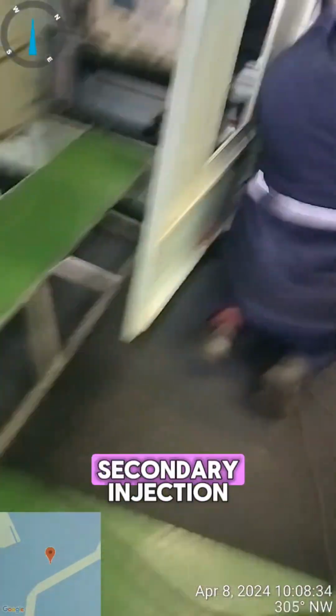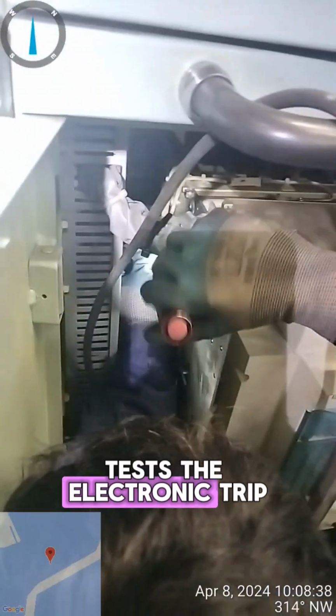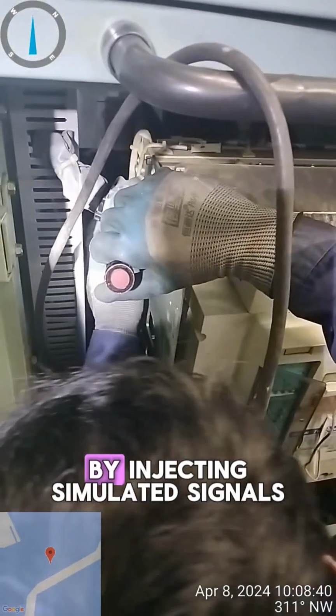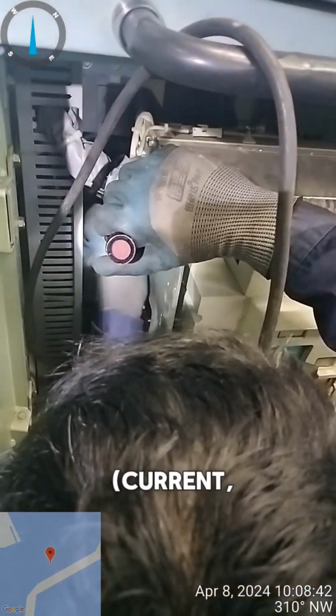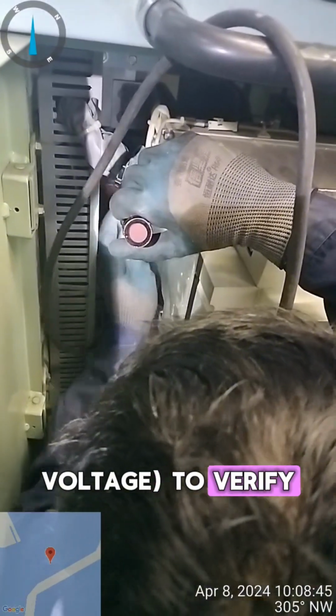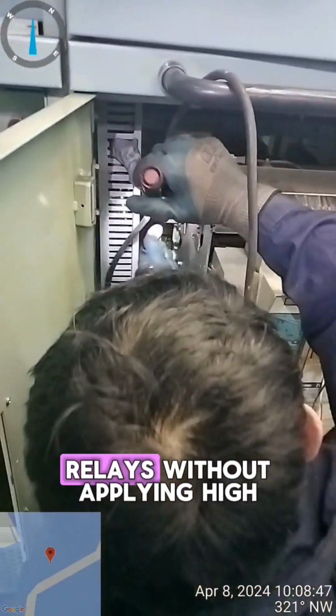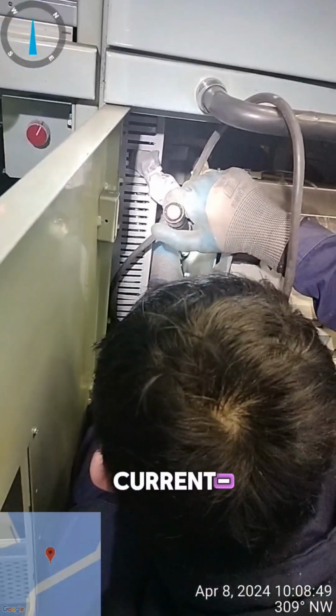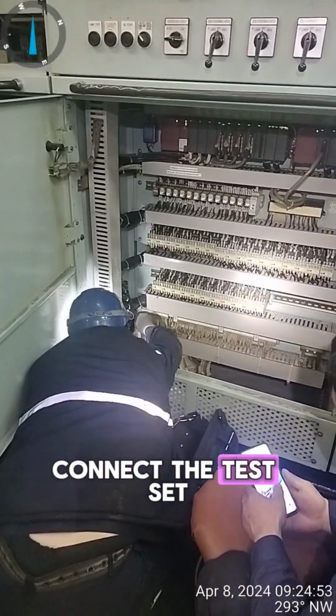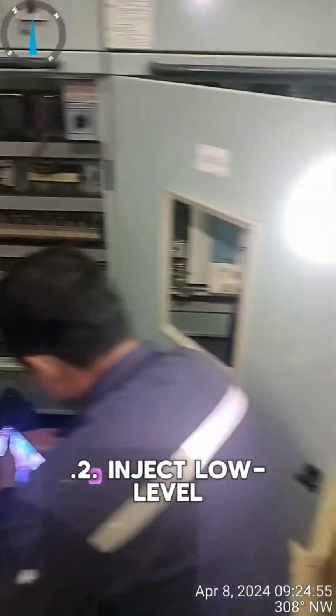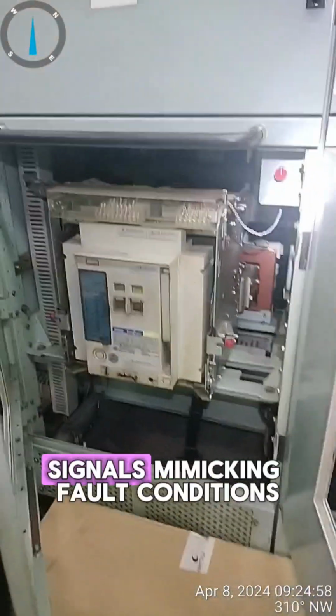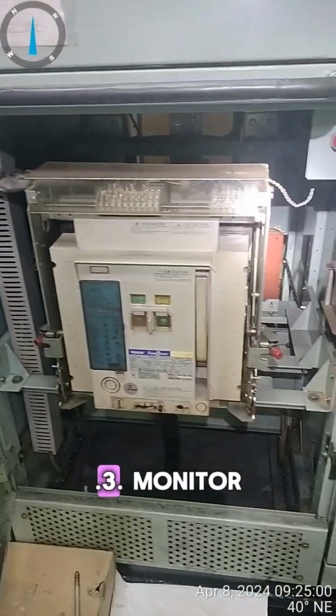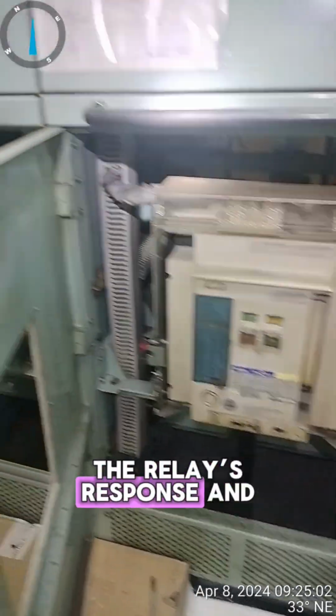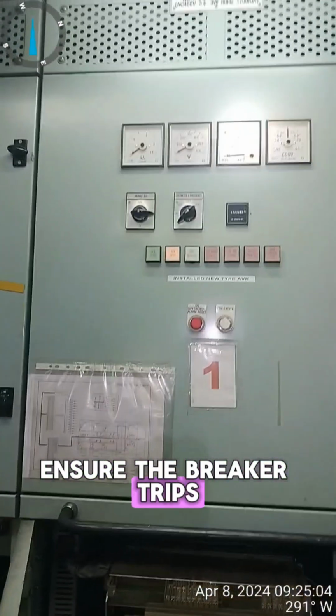2. Secondary injection test set. Function: test the electronic trip unit of the ACB by injecting simulated signals, current, voltage, to verify the operation of protective relays without applying high current. Steps: 1. Connect the test set to the trip unit. 2. Inject low-level signals mimicking fault conditions. 3. Monitor the relay's response and ensure the breaker trips as required.